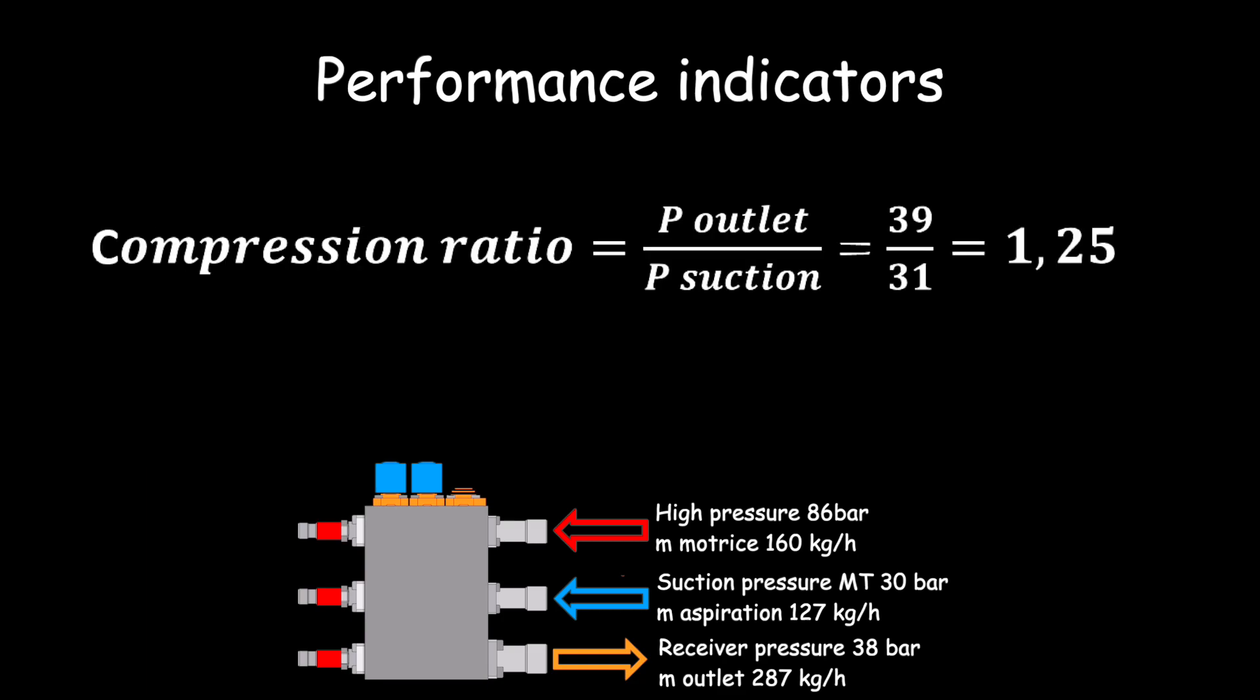Like a compressor, an ejector has a compression ratio; it is the second indicator of performance. With 39 bars at the outlet for 30 bars at the lift, the compression ratio is 1.25.